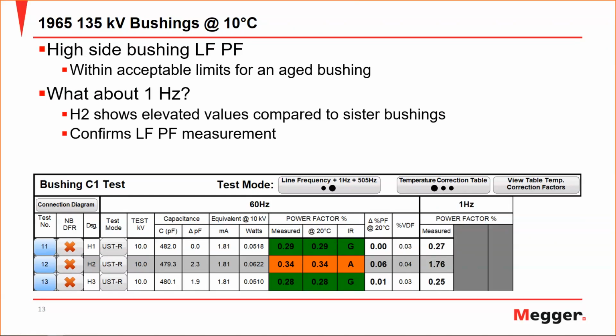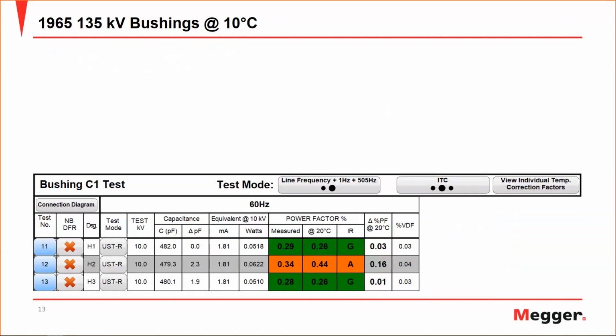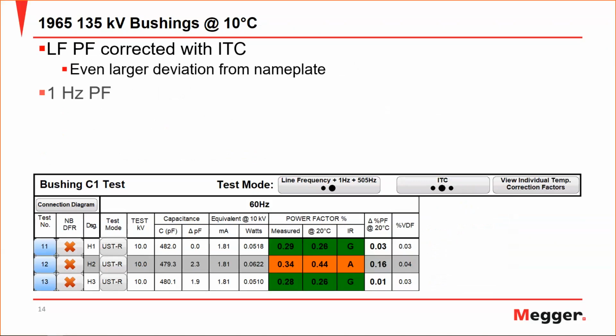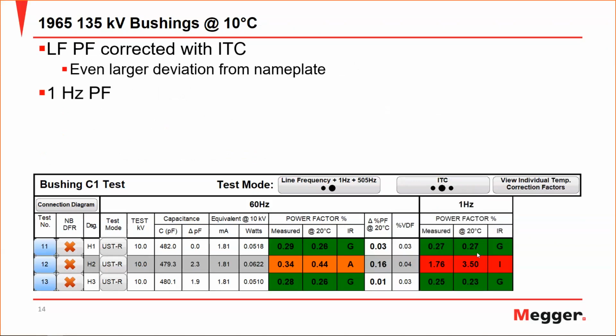And this elevated value then confirms the elevated value seen at line frequency power factor. But if we take it one step further, we can use the ITC, and we now see that the H2 bushing is deviating quite a bit more from nameplate than when we use those outdated temperature correction tables. And looking at 1 Hertz, when we correct back to 20 degrees C, the change is now much more drastic, 7 times measured versus 15 times different for this bushing here that has gone bad.